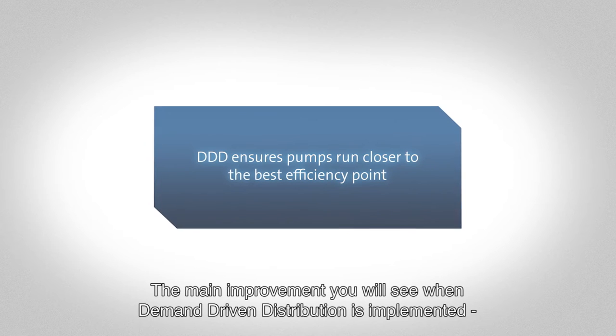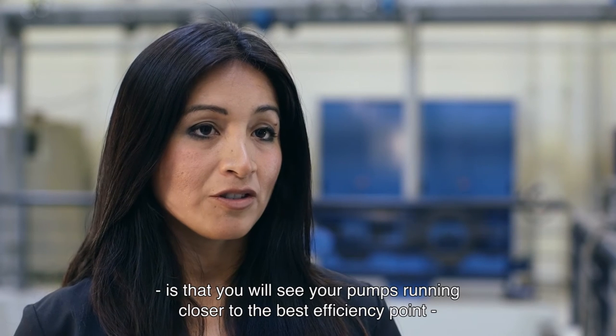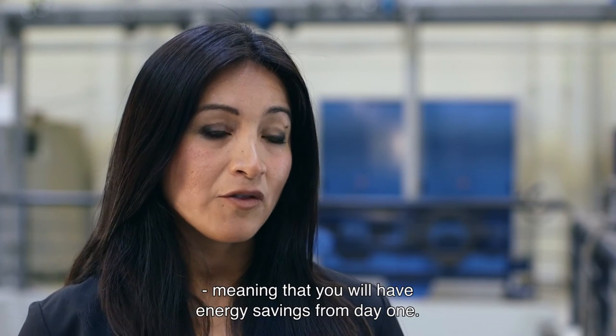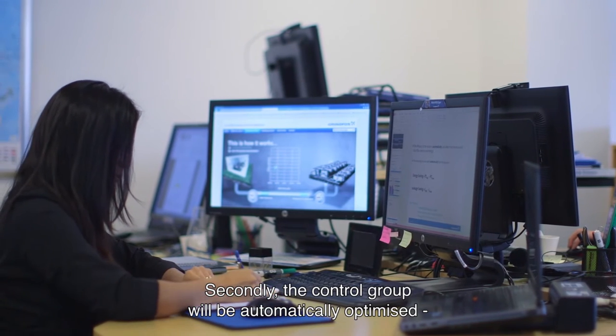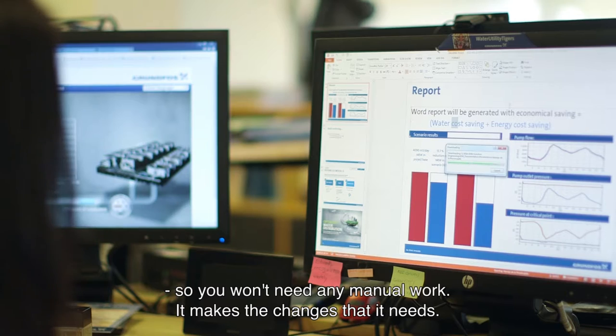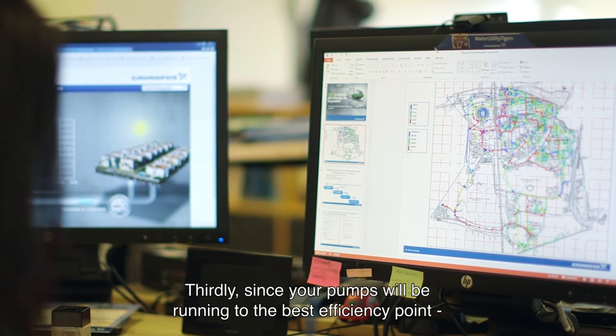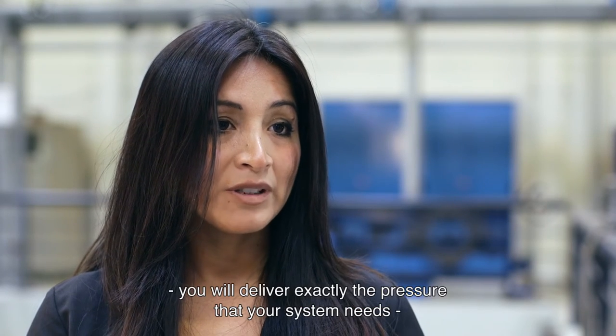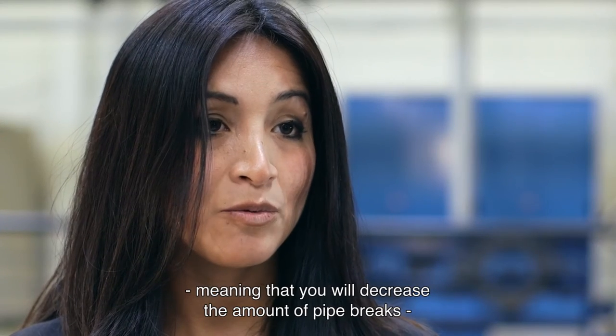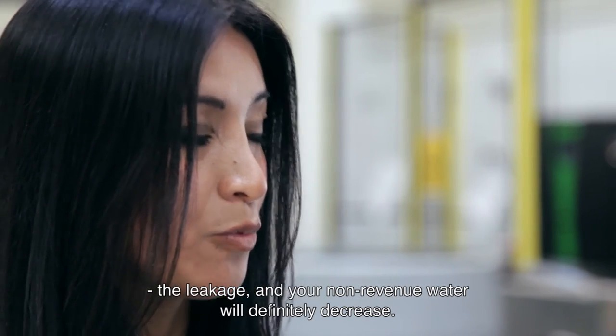The main improvements you will see when Demand Driven Distribution is implemented is that your pumps will run closer to the best efficiency point, meaning you will have energy savings from day one. Secondly, the control pool will be automatically optimized, so you won't need any manual work to make the changes it needs. Third, since your pumps are running at the best efficiency point, you will deliver exactly the pressure that your system needs, meaning you will decrease the amount of pipe breaks and leakage.